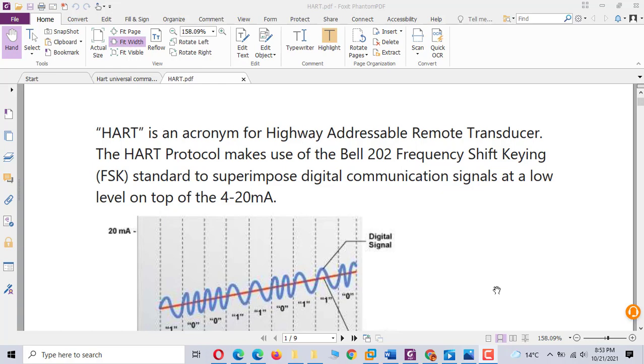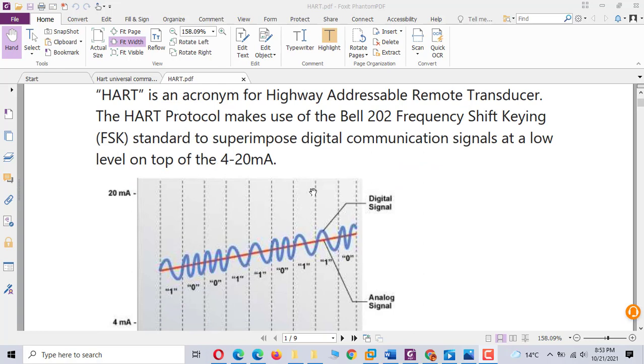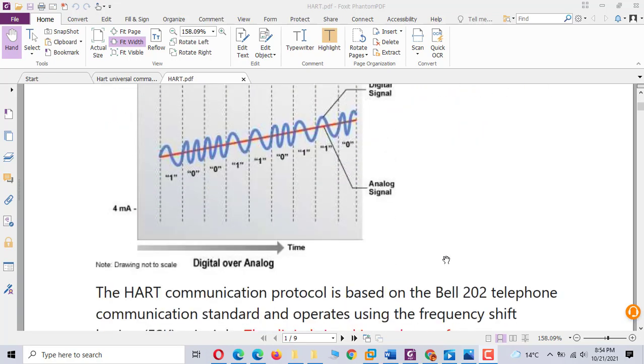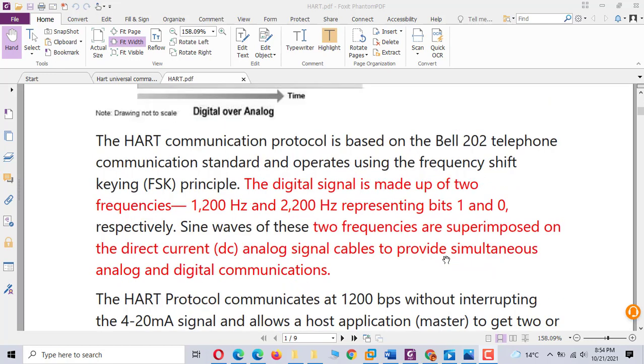HART communication uses frequency shift keying, FSK, and superimposes a digital communication signal on the 4 to 20 mA analog signal. The HART digital signal has two frequencies, 1200 Hertz and 2200 Hertz. 1200 Hertz represents 1 bit and 2200 Hertz represents 0 bit.